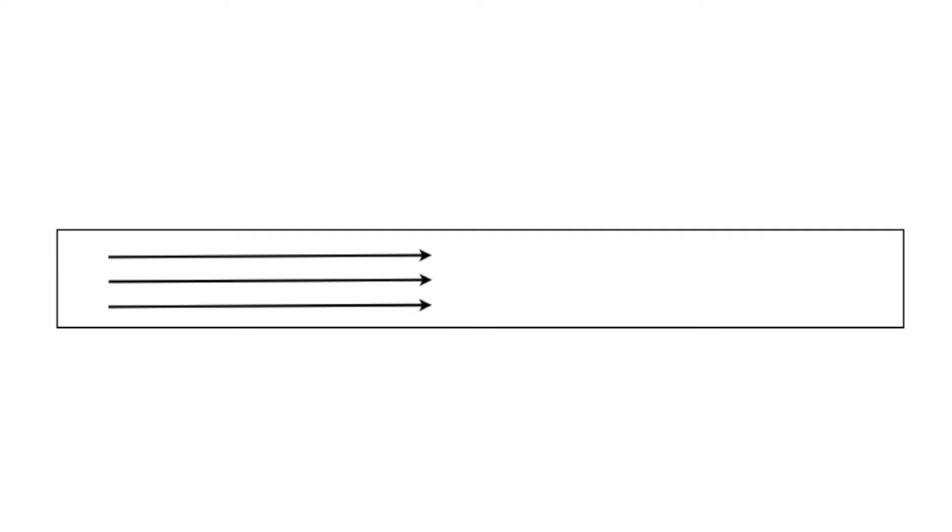Where we do get into a problem is in the suction line. Now suction line is of course larger than the liquid line simply because it's a gas instead of a liquid. You can move a lot more liquid in a small line than you can gas in a small line. So you'll increase the size of it. Now what we're trying to do here is we're trying to decide what size it should be.